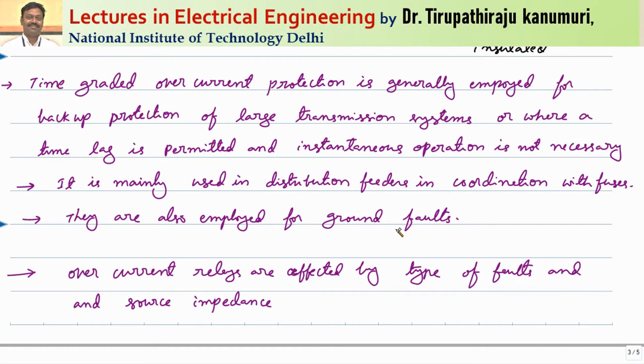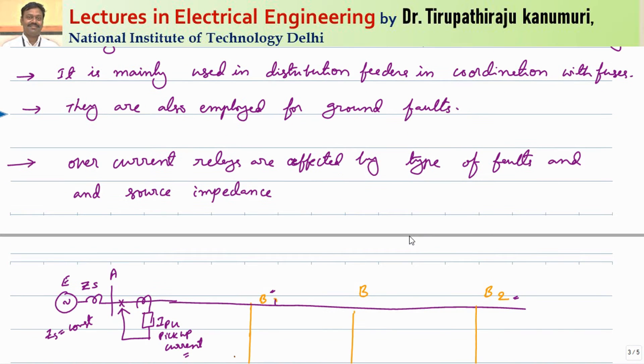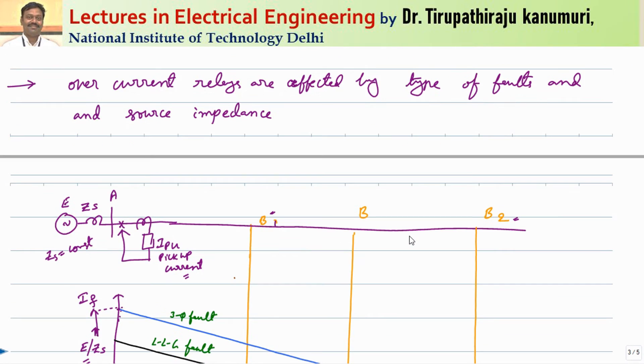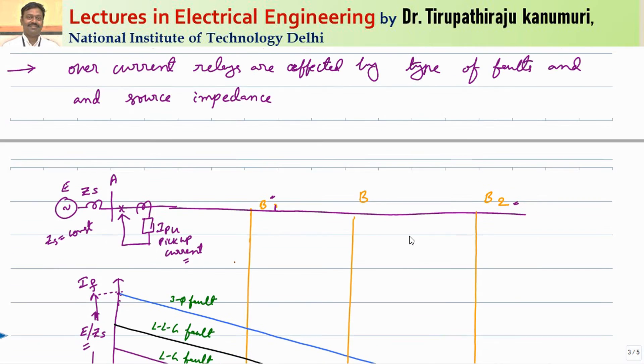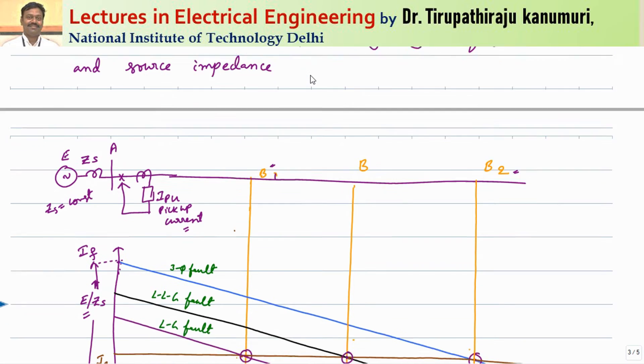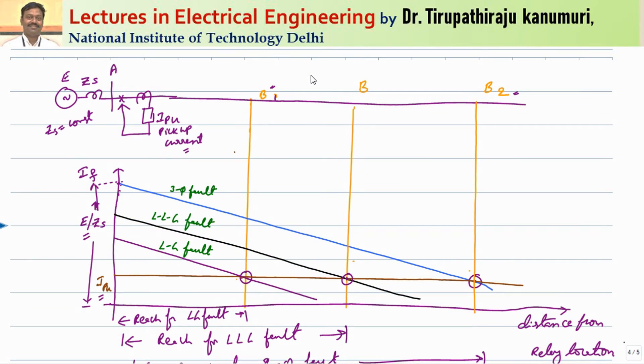These overcurrent relays are also employed for protection against ground faults. The main reason we do not use overcurrent relays for long transmission lines is that they are affected by the type of fault and the source impedance. Whenever the system capacity is increased, you have to change the settings or replace the overcurrent relay. That is the first disadvantage. The second disadvantage is they are affected by the type of the fault, so we cannot fix the value of the current very easily.